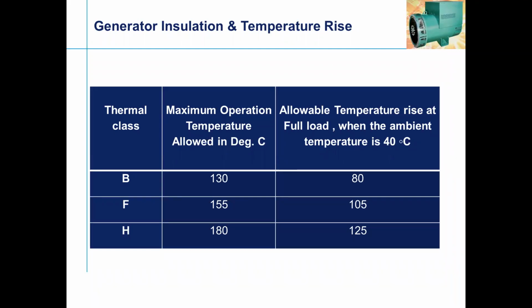Of course, in India, as I said, there is 48 degrees in Rajasthan, and at some points in Andhra, Vijayawada, as well as Nagpur, the temperature can touch about 49 or 50. So in those areas where the summers are like that, class H insulation becomes predominant, where the generator canopy and other things can see temperatures of even 45 to 50 degrees. So generally the customer requirement has moved on from the very late 80s. We had about class B.